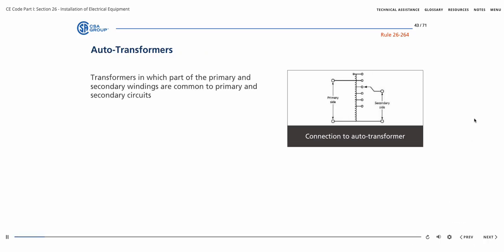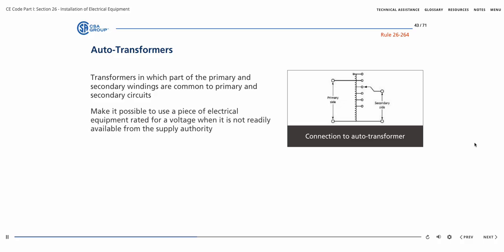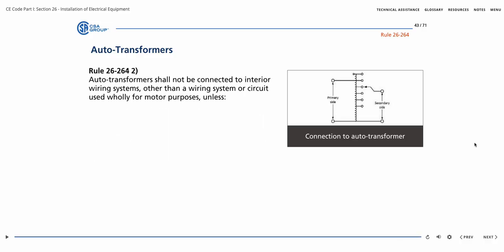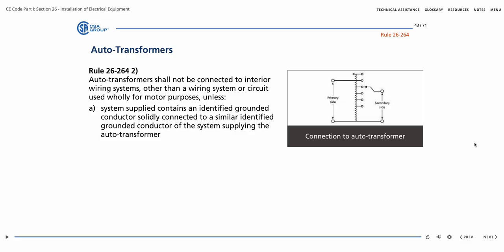Auto transformers are transformers in which part of the primary and secondary windings are common to primary and secondary circuits. The use of an auto transformer makes it possible to use a piece of electrical equipment rated for a voltage when it is not readily available from the supply authority. However, an auto transformer does not provide electrical isolation between its windings, primary and secondary, as a power or distribution transformer does. As a result, Rule 26-264 requires auto transformers to not be connected to interior wiring systems, other than a wiring system or circuit used wholly for motor purposes, unless the system supplied contains an identified grounded conductor solidly connected to a similar identified grounded conductor of the system supplying the auto transformer.